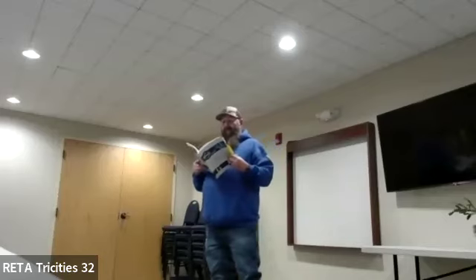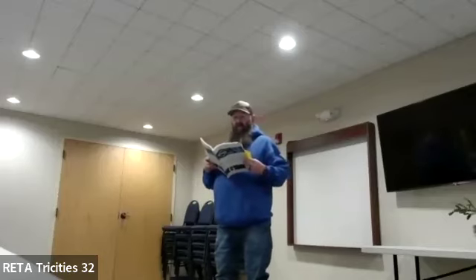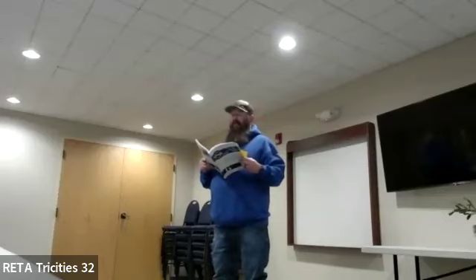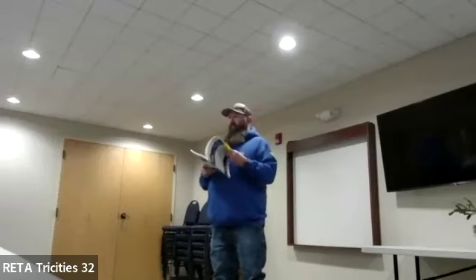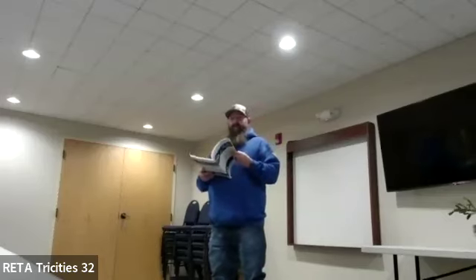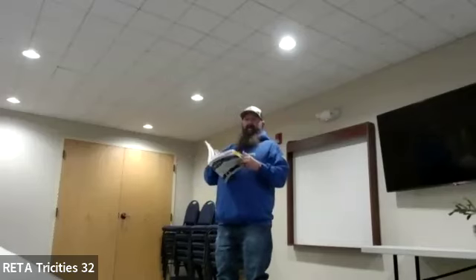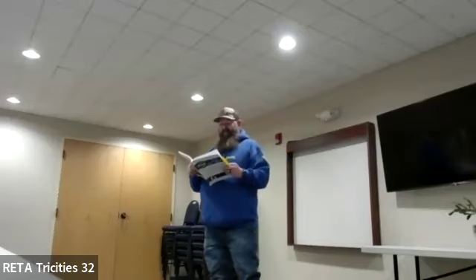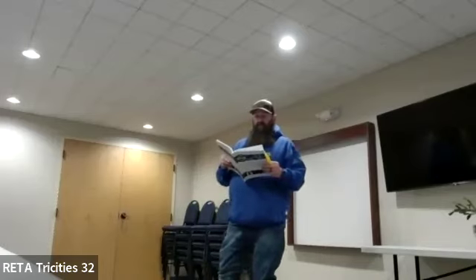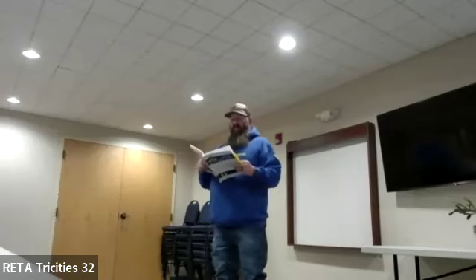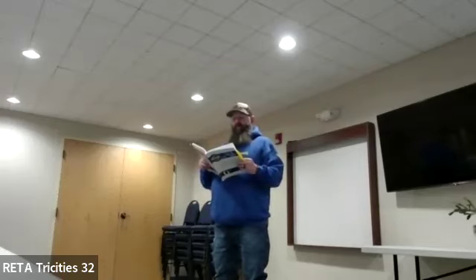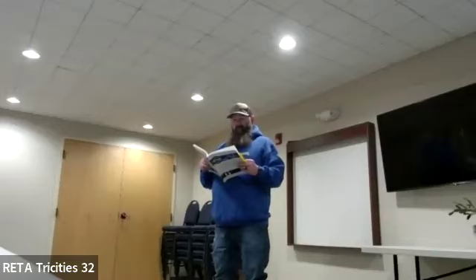Some of these, we may think they're all quirky, and I'm sure some plant controllers want to lose their mind when they have to spend the money. I just never even thought about 300 gallons per minute per eyewash station. No, 20 gallons. But 300 gallons total, if you don't have a hot water heater, you need 300 gallons per eyewash station. So if you have two in the engine room, you have two exits like you're supposed to, and you have to have them outside. That's a lot of water. You need 1,200 gallons or something like that right there.